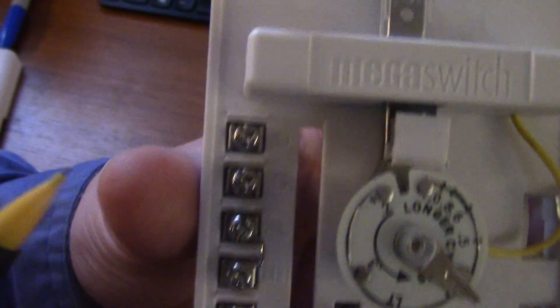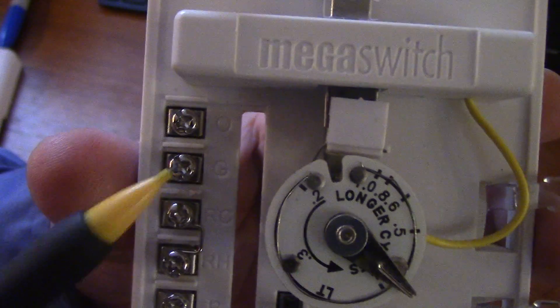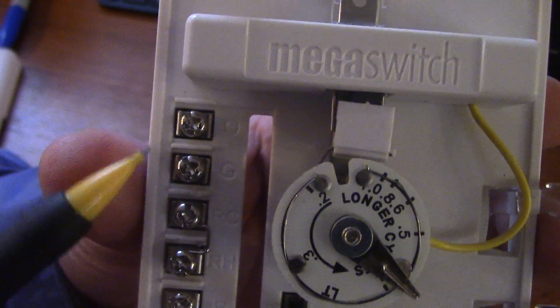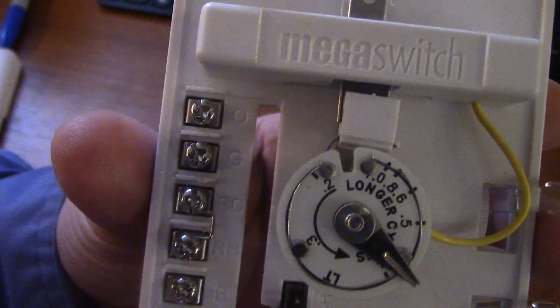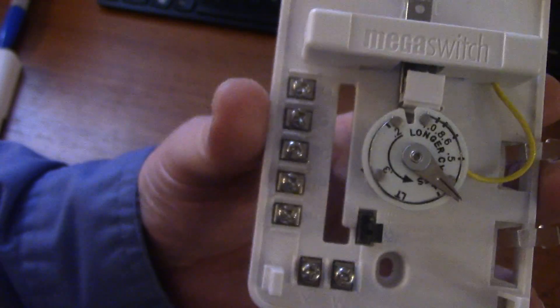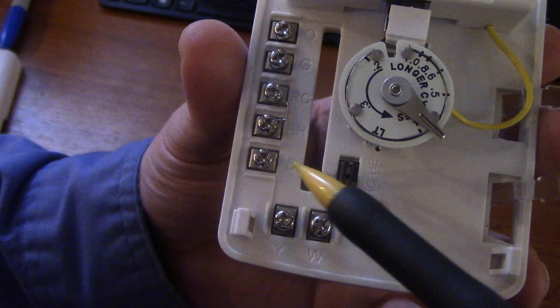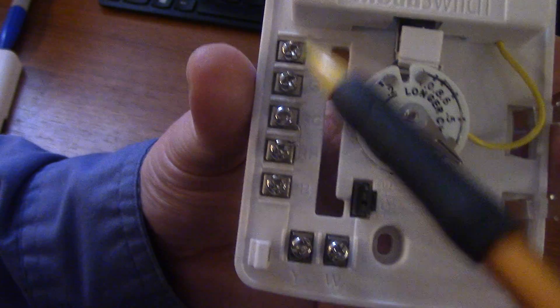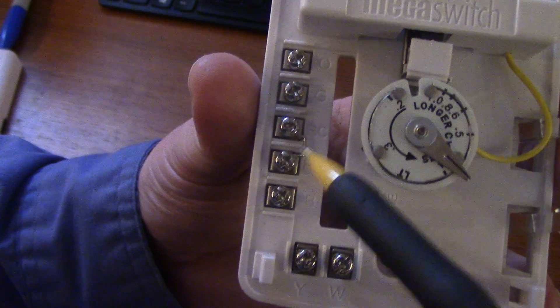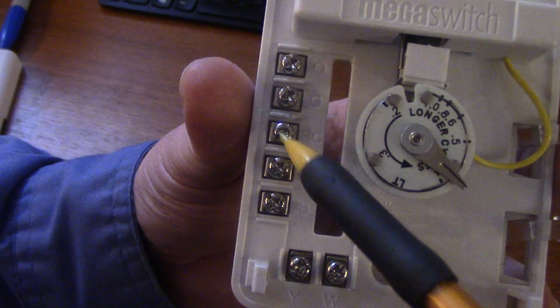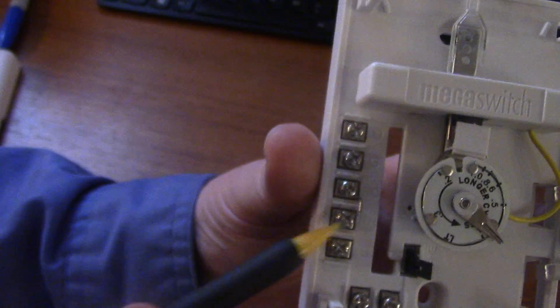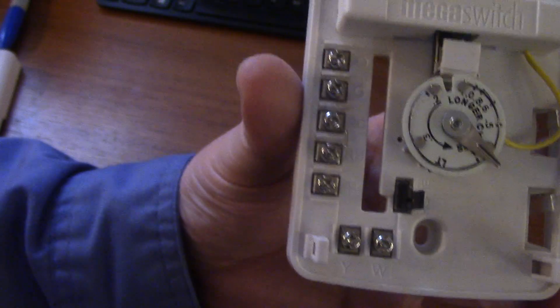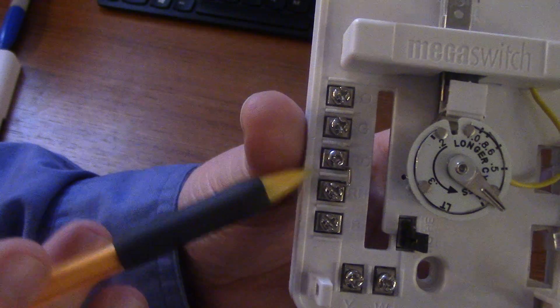This tab right here is G - that's where a green wire will go for fan operation. O is an orange wire, that's for heat pump reversing valve. So yellow is cool, W is heat, B will be blue, O will be orange, G will be green, and the red wire goes to RH RC. As long as you have that jumper wire there, it does not matter what wire terminal it gets hooked to because that jumper is going to make it happen.